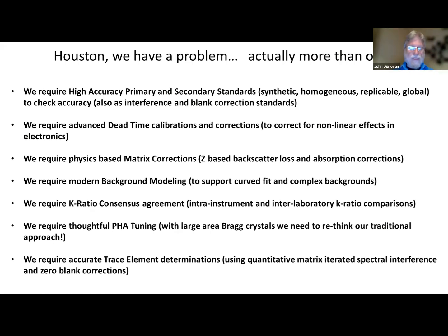And we need to use quantitative interference corrections with zero blanks for accurate trace element determinations. Can you measure zero? We always test with the analytical total whether we can measure 100%, but we need to test zero as well.